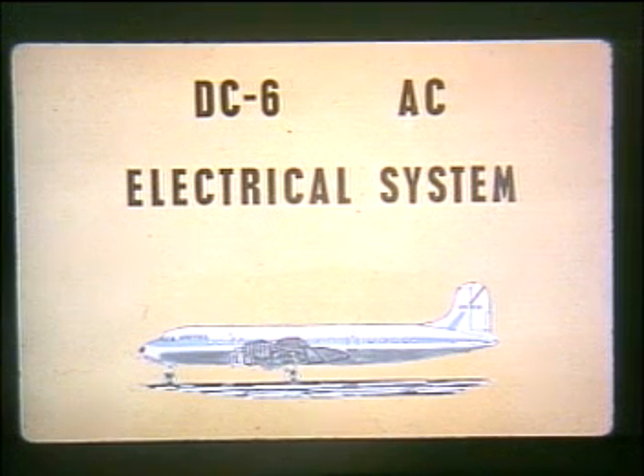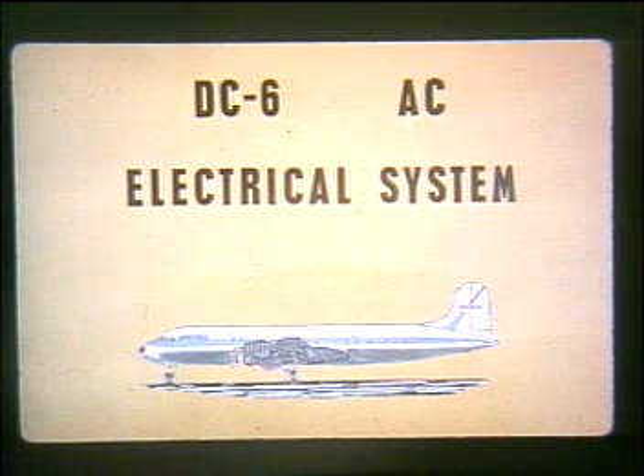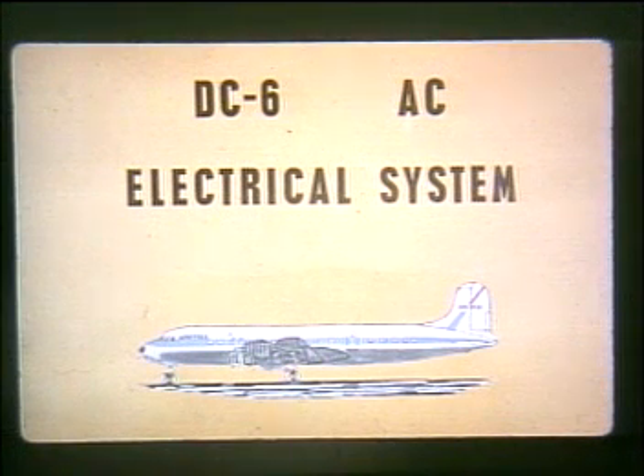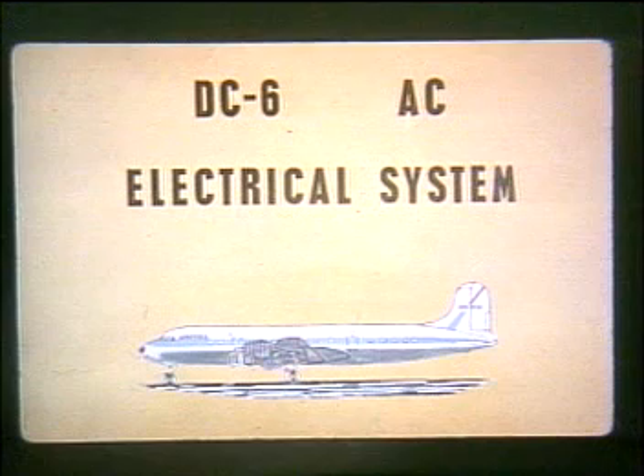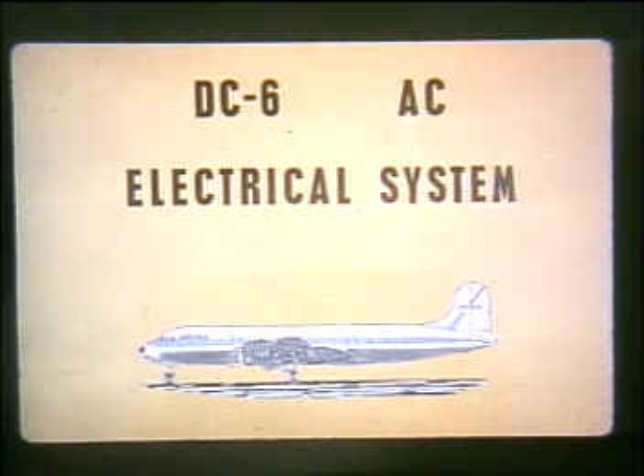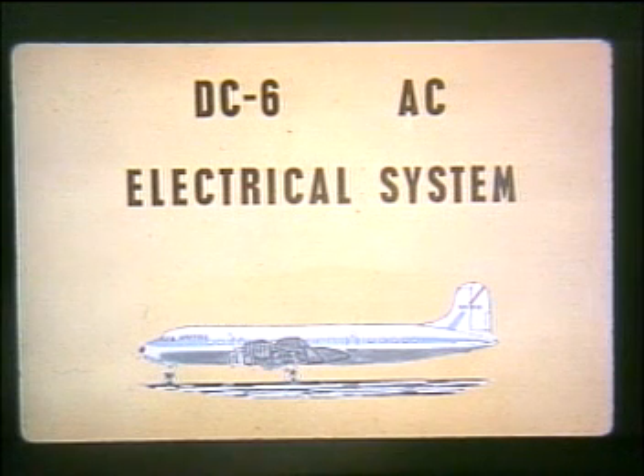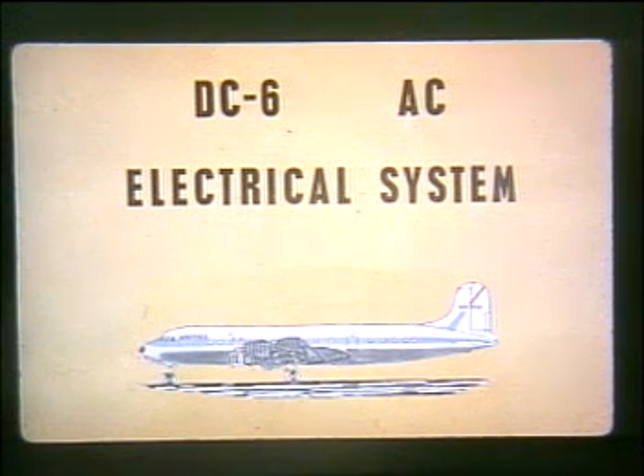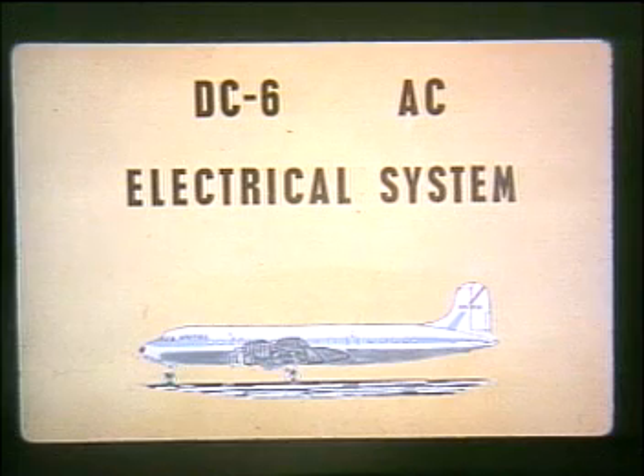To provide the necessary alternating current for the DC-6 aircraft, two direct current-driven rotary inverters are installed to furnish 115-volt AC, 400-cycle, three-phase power. A small vibrator-type inverter furnishes 110-volt AC, 60-cycle, single-phase current with sufficient power to operate 5 electric razors. The AC electrical system of the DC-6 varies slightly between the Group 1 and Group 2 aircraft, as does the DC system. We will discuss the Group 1 AC electrical system and incorporate the changes in the Group 2 system later in this presentation.